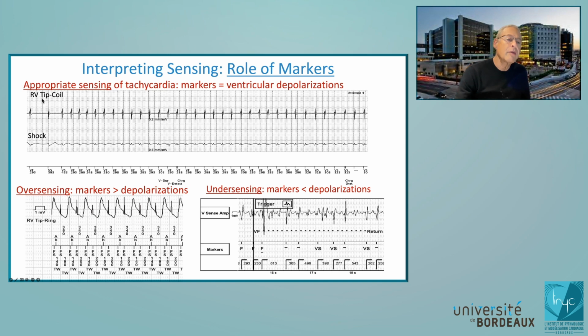When you look at an electrogram, the first question is, what are the channels recorded? What leads in the heart are we showing? And here we show a right ventricular sensing lead, sensing channel, and we show the shock channel between the two shock electrodes. And we show a marker channel. The marker channel identifies sensed events. Devices, as long as the telemetry is working correctly, will deploy a marker for each sensed event and usually put some timing interval on it and maybe even label a classification like what type of detection zone it puts it in. Here, these events are in the ventricular fibrillation zone.